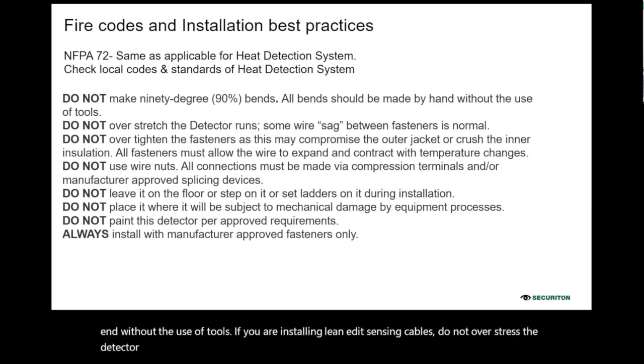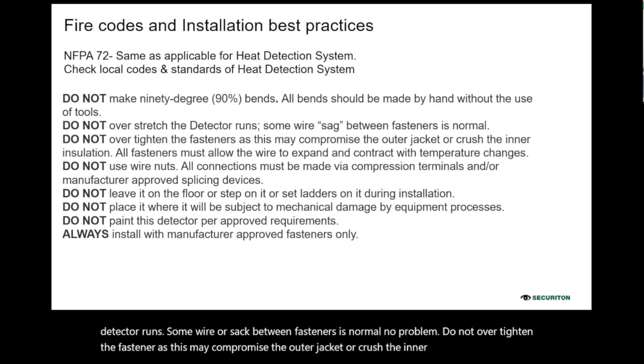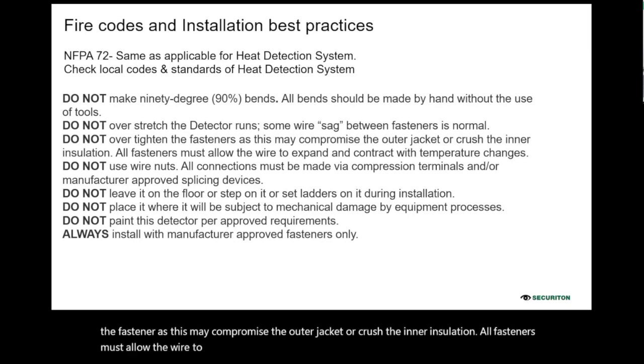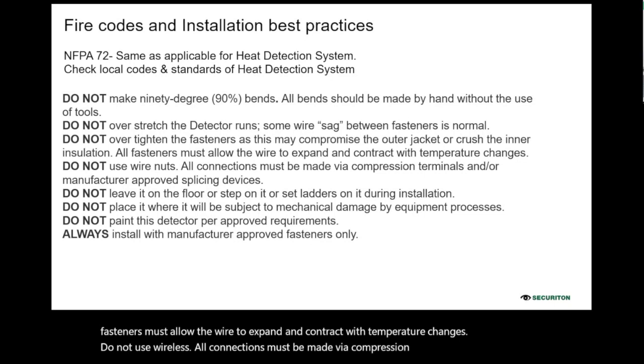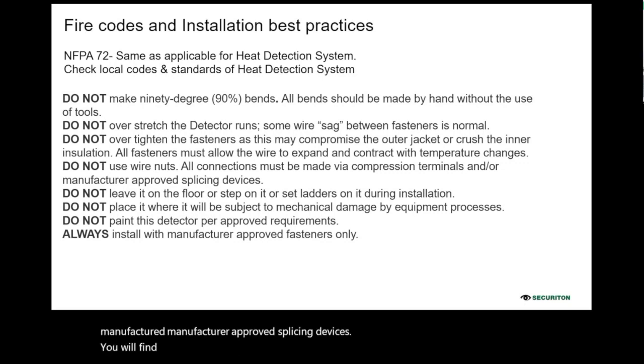Some slack or sag between fasteners is normal, no problem. Do not over tighten the fastener, as this may compromise the outer jacket or crush the inner insulation. All fasteners must allow the wire to expand and contract with temperature changes. Do not use wire nuts. All connections must be made via compression terminals and or manufacturer approved splicing devices. You will find the devices specific to the manufacturer.